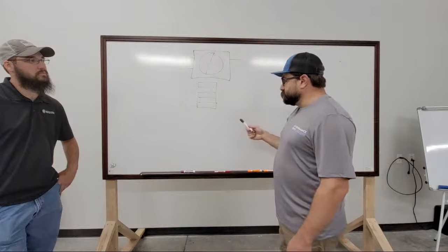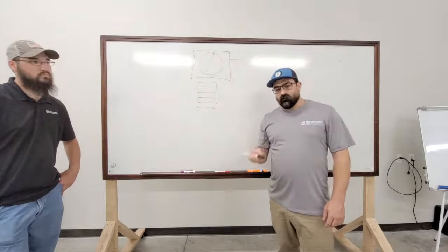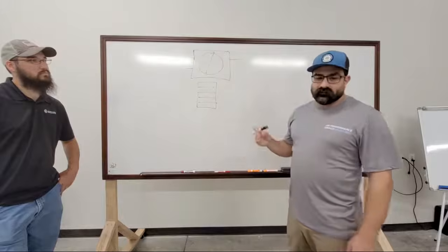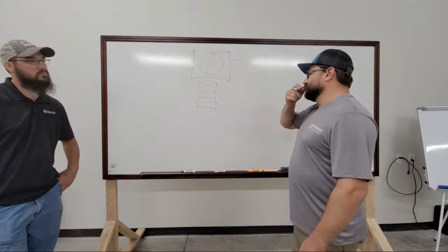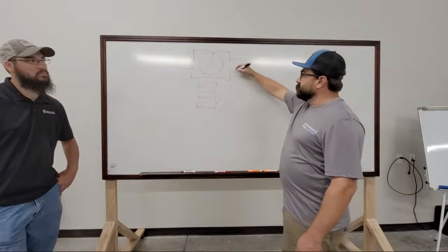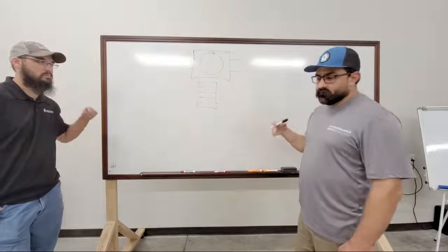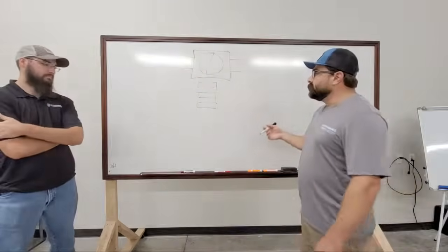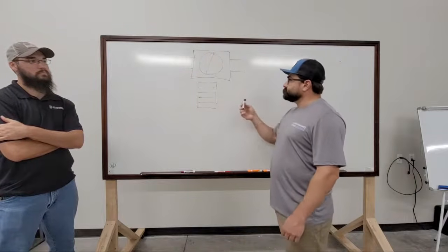There are two basic types of control for a VAV box. Well, actually, take that back. We'll touch on fan power boxes before we go down that road. So the simplest way to think of it is a VAV box is a variable air volume or variable volume terminal. It's just controlling the amount of air going through the box into the space.